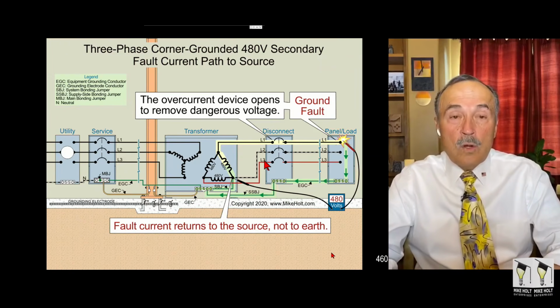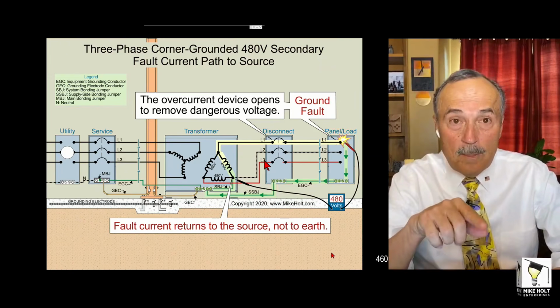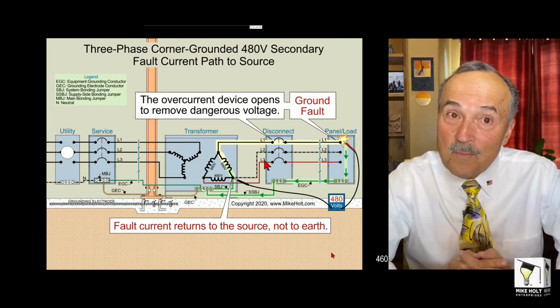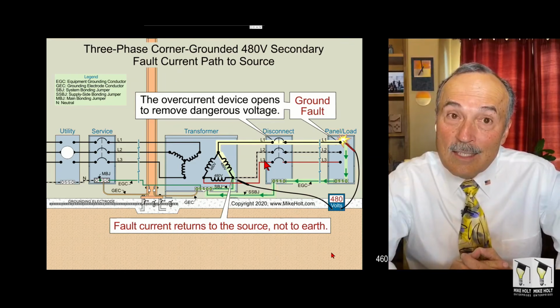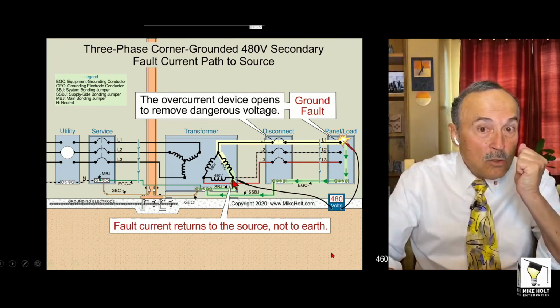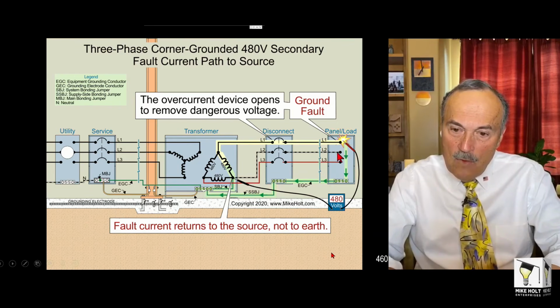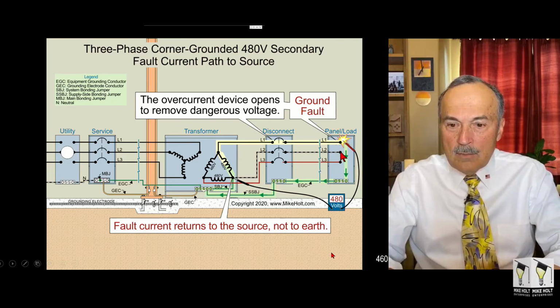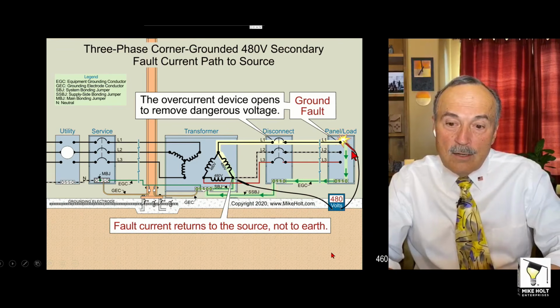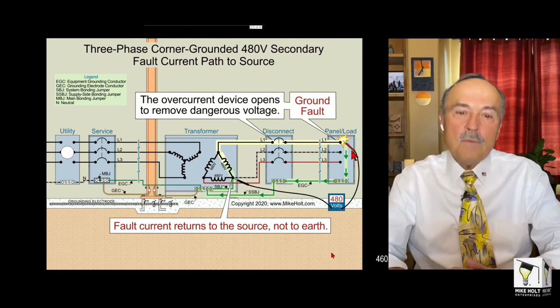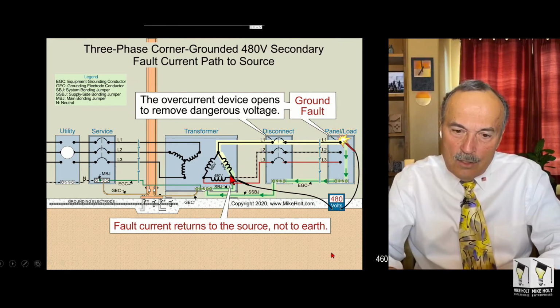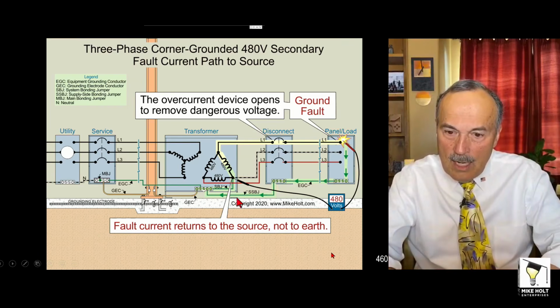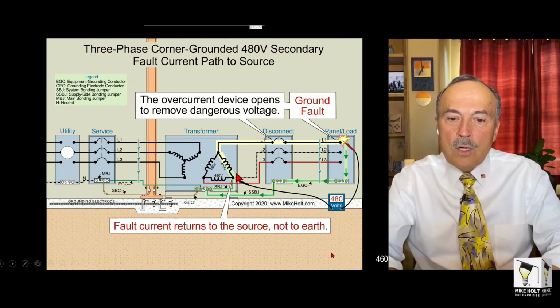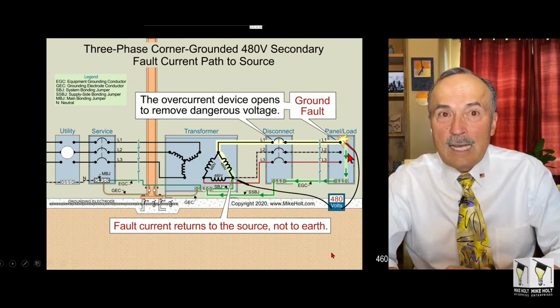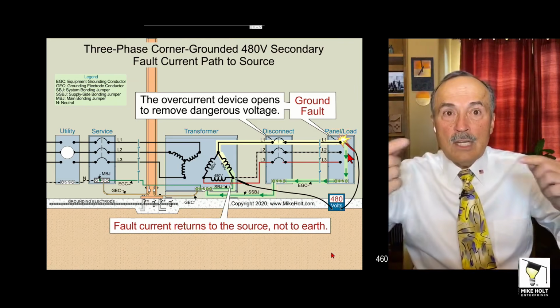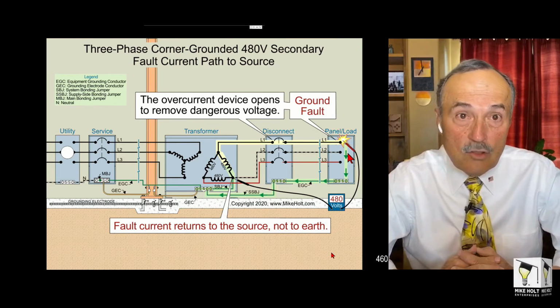How do you clear a fault on a corner grounded delta system? Well, if the phase that's grounded is faulted again, guess what you have? Objectionable current, right? If you have the neutral, it's not a neutral. If you ground this to the case here, and somewhere over here your grounded conductor inadvertently ground faulted, okay, well, you're going to have current. What you're going to have is currents traveling on line 2, the way the 3 phases work, and then you're going to have currents traveling on that. So on a corner grounded delta system, if the grounded phase itself faults again, then you are going to have a grounded conductor connection to the case at 2 locations, violating 250.6, objectionable current.